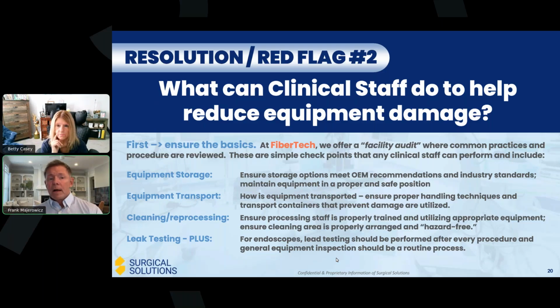Equipment transport. How is the equipment being transported, from SPD up to the departments, back to SPD, from the cleaning room into the procedure room, and from the procedure room back to the cleaning room? What are your handling techniques? What is it being transported in? Is it in the proper bin? Is it secured safely? You want to make sure there's not other equipment piled up on top of something that may be delicate. A lot of times we'll see a flexible endoscope with everything else used during that procedure in a bin piled up on top of it. Not something you want to do.